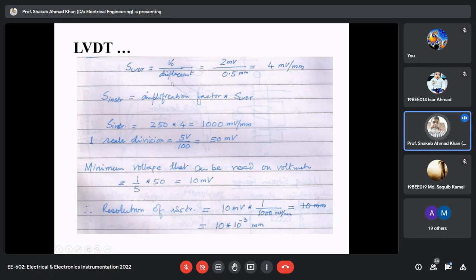So here you see the LVDT sensitivity is calculated. It is 4 millivolt per millimeter, and the amplification for the instrument is the amplification factor into the LVDT sensitivity. So it comes out to be 1000 millivolt per millimeter, or 1 volt per millimeter.